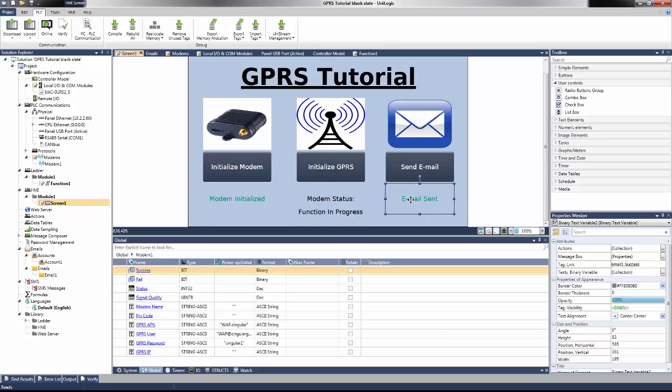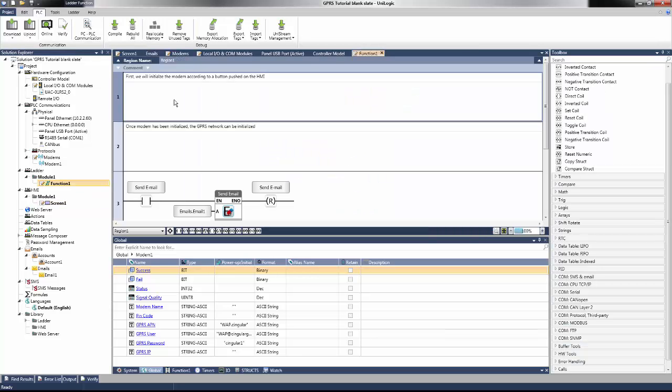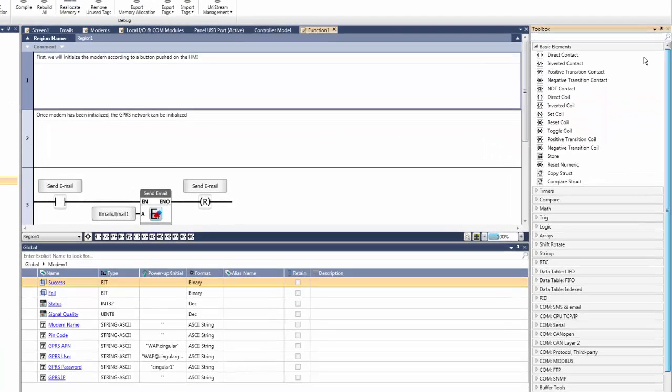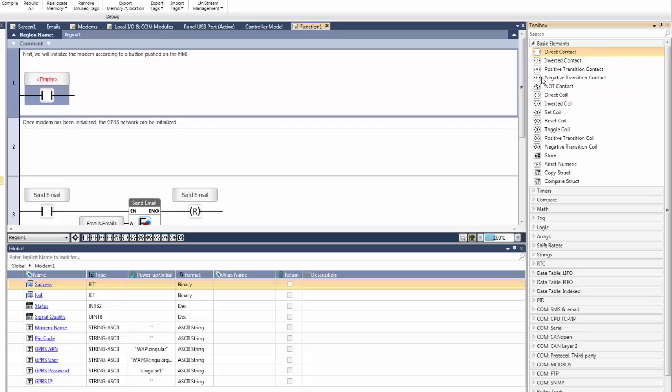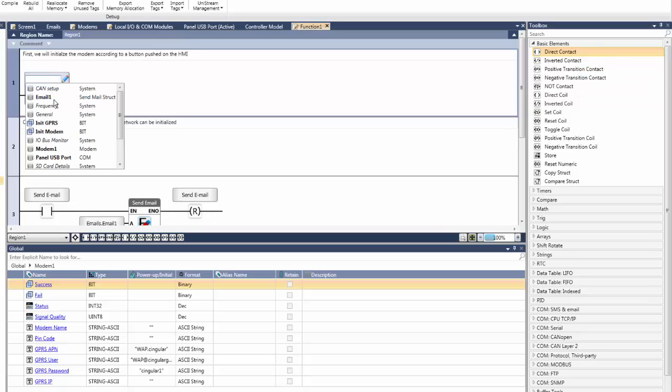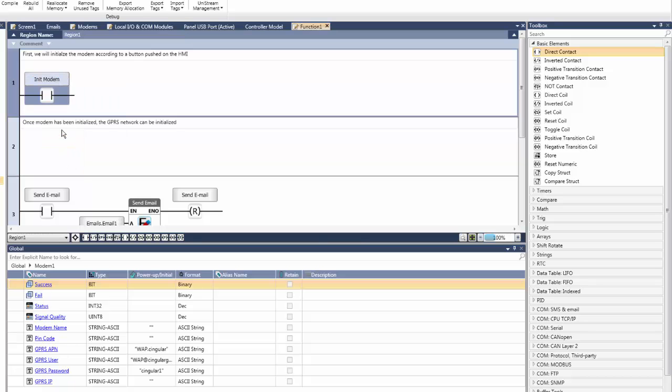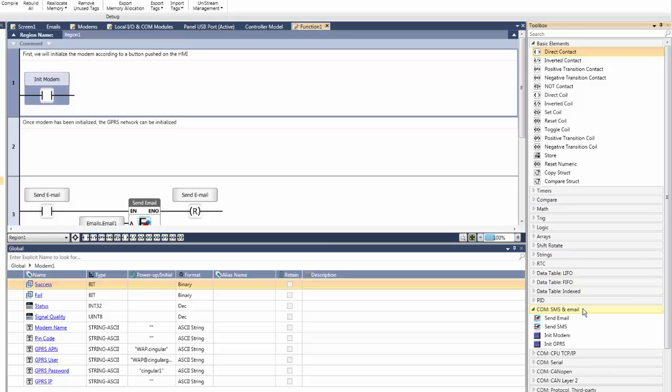Next, create the ladder to initialize the modem to the GPRS network. According to the button pushed on the HMI, first initialize the modem. Add a direct contact for this button, and link the bit init modem. Please note these bits were created in advance with the HMI screen. In series with the contact, add an init modem function block from under the com, sms, and email dropdown menu in the ladder toolbox.